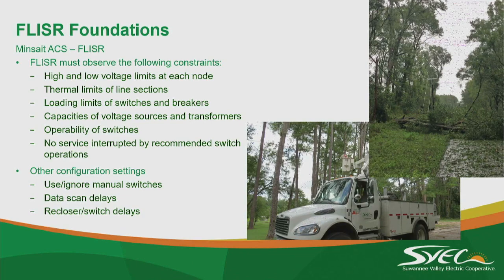It looks at your source transformers, making sure you have enough capacity, and the operability of switches is part of that communication. Is this switch in local mode or remote mode? Can we use it? Is it a hotline tag? Does it have comms? All of that goes into play, and it says, oh, we have a hotline tag on this device, this feeder's off limits to backfeed, so it blocks all of this.